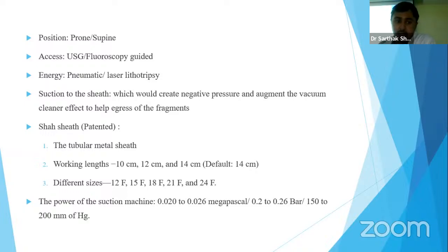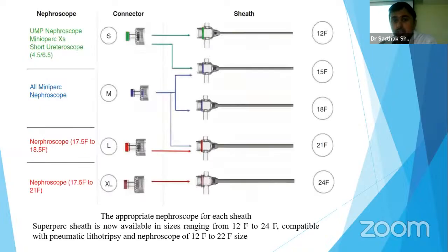An important point is the sheath comes in different working lengths of 10 centimeters to 14 centimeters and different sizes ranging from 12 French to 24 French. Power of the suction is usually kept at 150 to 200 millimeters of mercury. This diagram depicts all the available sheaths we have from 12 French to 24 French, and they have specific connectors which have been labeled as S, M, L, and XL according to the sizes. They can accommodate different types of nephroscopes ranging from 12 French to 22 French size.